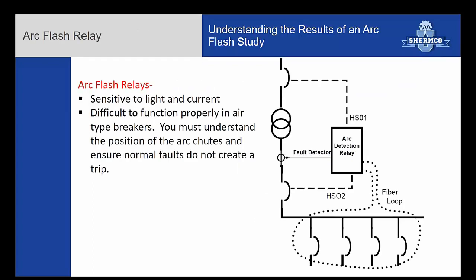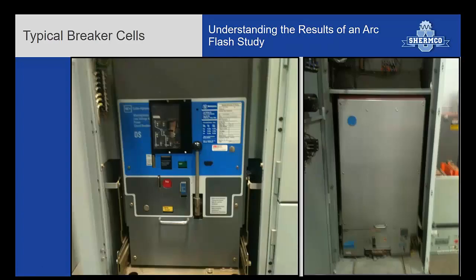Another great one is arc flash relays. What arc flash relays do, if you're trying to reduce your incident energy, is you put basically a fiber loop, something that's looking for light, that's just gathering light. So it's really just a fiber. They have spot sensors as well, but you run some fiber through your switchgear in the areas you're trying to protect. If you have light on that fiber and you have fault current levels, you get to determine what you want to set your fault level at. But if you have high current and light, then this relay would activate and trip whatever device you're tripping. So arc flash relays are very good. They can be misapplied. You have to be kind of careful.